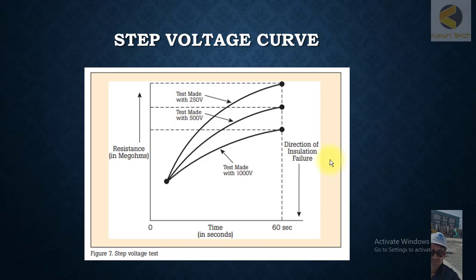Let us discuss how to analyze the curve for step voltage. Here you can see this is the step voltage curve, with a time of 60 seconds. We applied 250 volts and get this many mega ohms; at 500 volts we get this many mega ohms; and at 1 kV we get this many mega ohms.